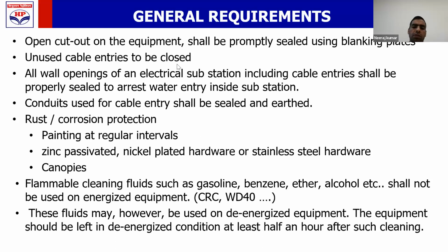All of us must be using CRC, WD-40 or similar kind of thing. If those materials have flammable liquids such as gasoline, benzene, ether, alcohol, then those liquids should not be used on live electrical equipment. You can apply these liquids only on de-energized electrical equipment. Even if you are applying them on de-energized equipment, you should not immediately switch on that equipment. You should wait for these flammable liquids to vaporize and go away. The minimum time required is 30 minutes.